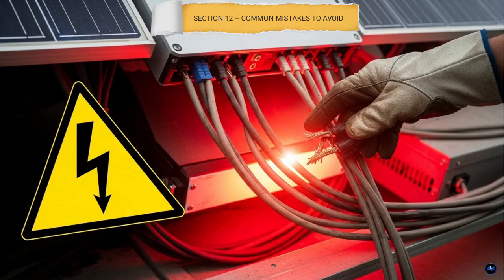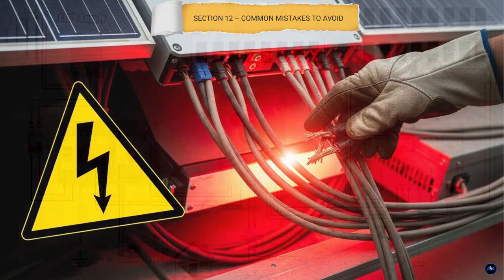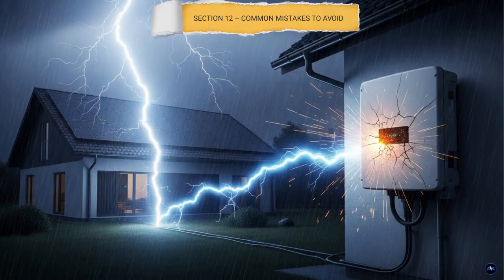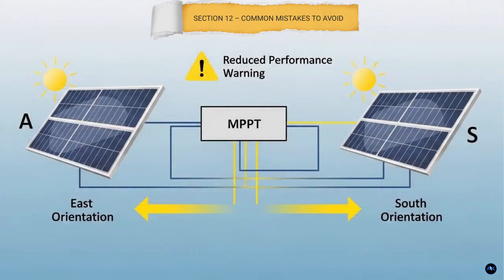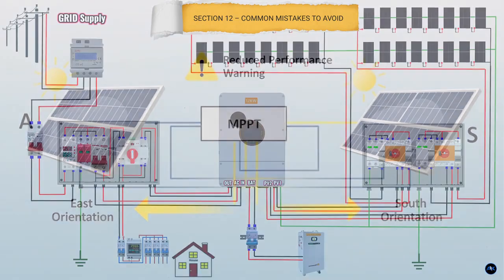Another very common mistake is not installing a DC isolator. Without a DC isolator, you cannot safely shut down the solar array for maintenance or emergencies. Skipping surge protection is also dangerous. Lightning and grid surges don't need a direct strike to cause damage. Without DC and AC surge protection, your inverter and electronics are exposed. Another mistake is mixing different panel orientations or tilt angles on the same MPPT. For example, east-facing and south-facing panels should never be connected to the same MPPT because they produce power differently and reduce overall system performance. Avoiding these mistakes can save you money, prevent equipment damage, and keep your system safe.